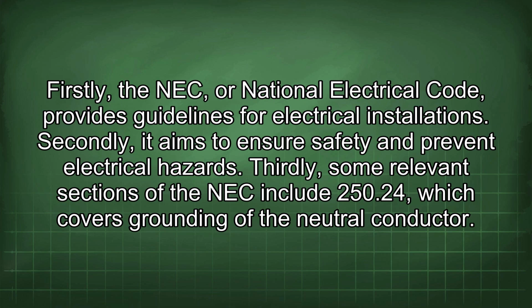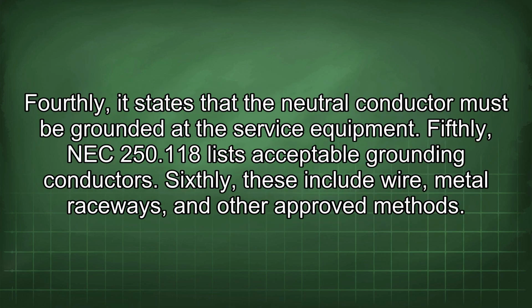Firstly, the NEC, or National Electrical Code, provides guidelines for electrical installations. Secondly, it aims to ensure safety and prevent electrical hazards. Thirdly, some relevant sections of the NEC include 250.24, which covers grounding of the neutral conductor. Fourthly, it states that the neutral conductor must be grounded at the service equipment. Fifthly, NEC 250.118 lists acceptable grounding conductors.